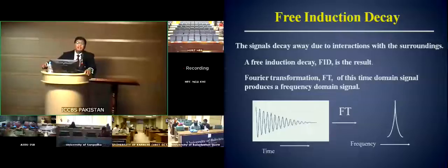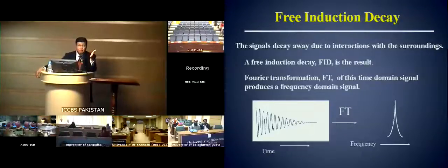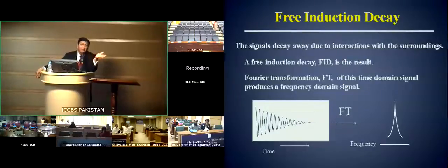Not the shimming. Shimming is altogether different. It's a deuterium lock for chloroform. Because we've already set a deuterium lock for chloroform, you'd like to do all the CDCl3 samples one after the other. Because if you change one after the other, every time you have to redo it.